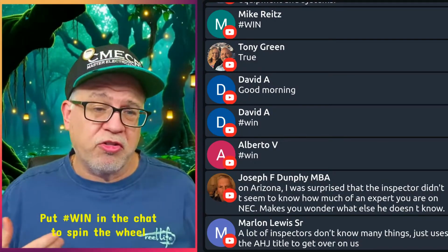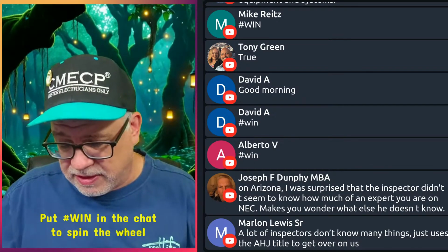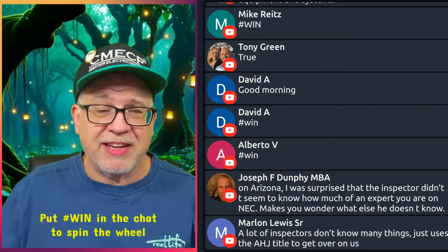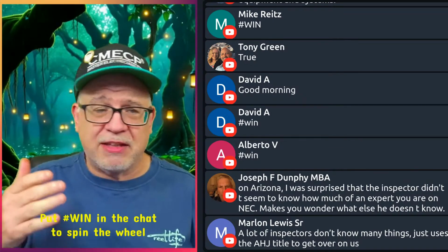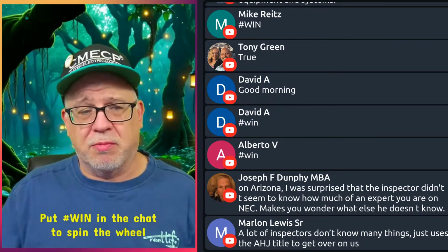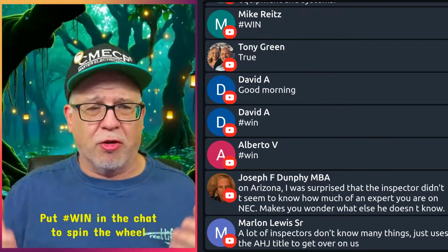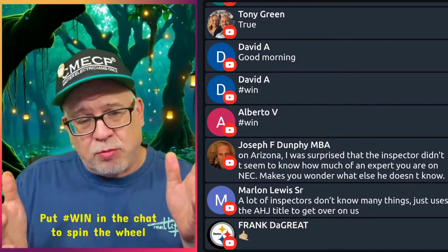So what is my solution? I might be an electrician and I might go, well, let's see here. My recommendation, if it keeps tripping, might be to divide those loads up and try to distribute them out a little more for that specific breaker. I'm not going to redo your whole panel if that's the only one you're having a problem with. That's what I'll do.